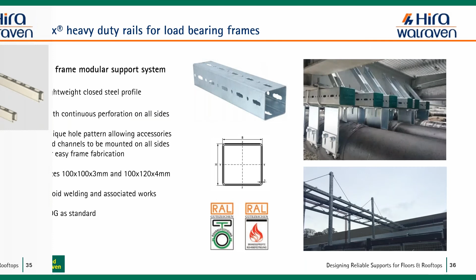Heavy duty rails, from the name of it, are for heavy duty applications: big diameter pipes, chilled water pipes, big size ducts, mainly smoke management ducts that have very heavy weights. This profile is a closed profile that's perforated on all sides, and it has a unique hole pattern to allow the accessories and channels to be mounted on all sides of this profile. It's available in 3 sizes. Previously it was 2 sizes: 100 by 100 by 3 mm and 100 by 120 by 4 mm, and we recently introduced a new size which is 80 by 80 by 3 mm as well.